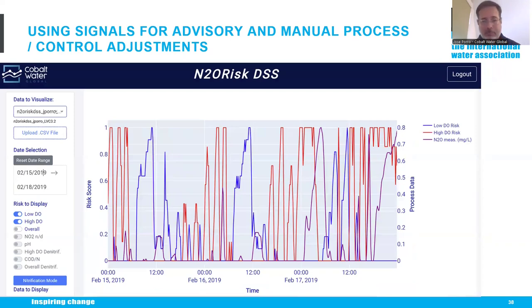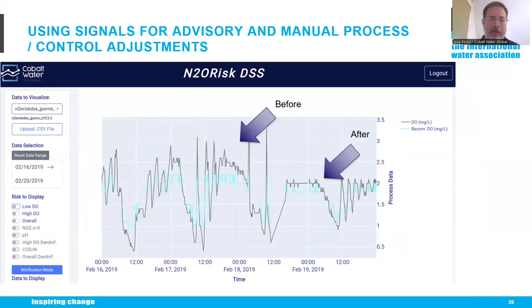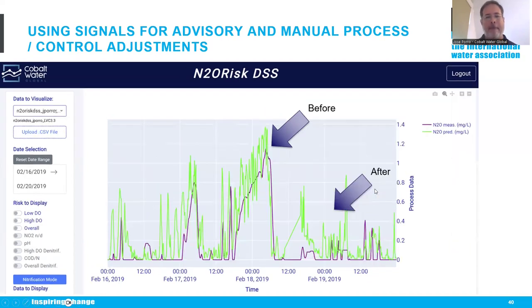Another example of advisory level control: based on ABAC — ammonia-based aeration control — we saw N2O being produced during both low DO and high DO risk periods. The DO was frequently both above and below what would be recommended because ABAC operates between a low and high DO set point. Based on this, informed adjustments were made manually to bring it in line with what was recommended, and we saw an immediate drop in N2O. In this particular case in the Netherlands, it resulted in a 90% reduction.